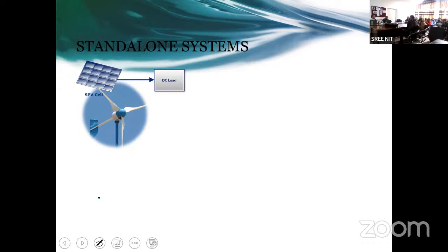But if you are having a solar powered submersible pump, then the power generated by solar depends on the irradiation level. So if radiations are changing, the power is changing. Power is changing, the speed of the machine is also changing. So if the speed of the machine is changing, then ultimately the flow of water, the discharge level of water, is going to change. So these are the directly fed loads, where it doesn't matter if there is a variation in discharge level, because ultimately the power is coming out free of cost. Water is coming out free of cost because of the solar panel. So these are the directly connected loads.